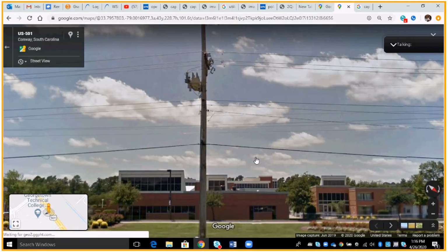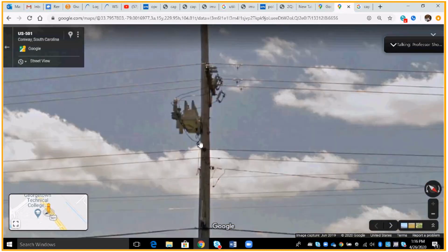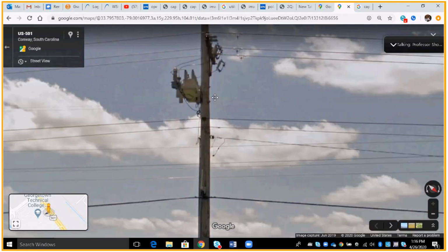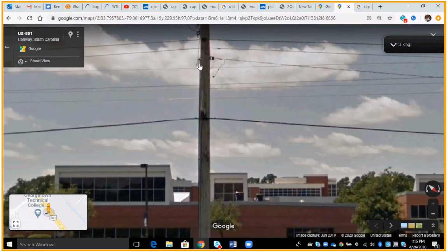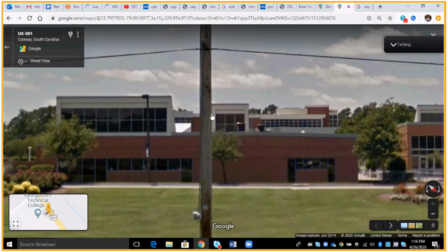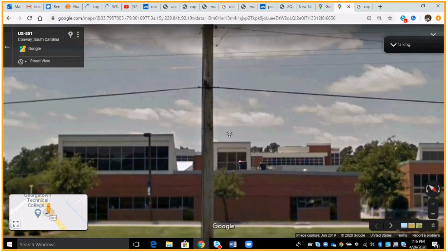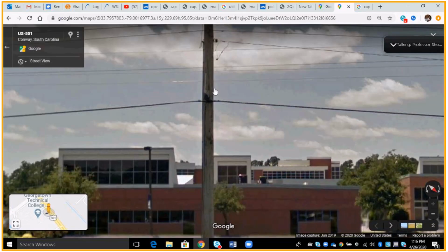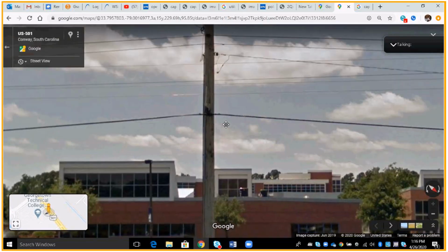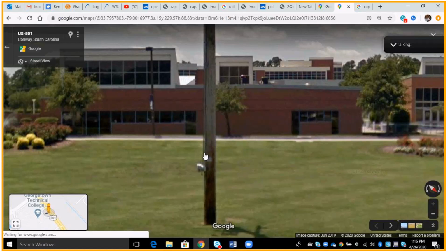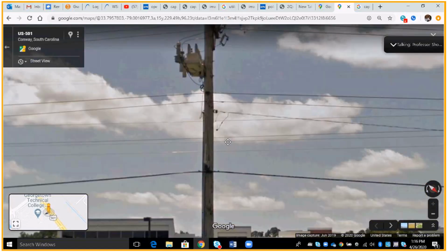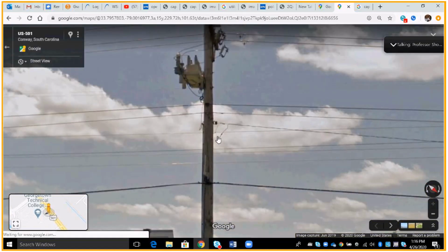See, this is pretty good right here. Capacitor bank control cables come down, actually go into this piece of conduit, down to the control box. And to help reception right here, they've installed an antenna that can receive the signal. And that control box has the wires in it to come back up here and say open and close the bottles. So this is fully automated in this instance.